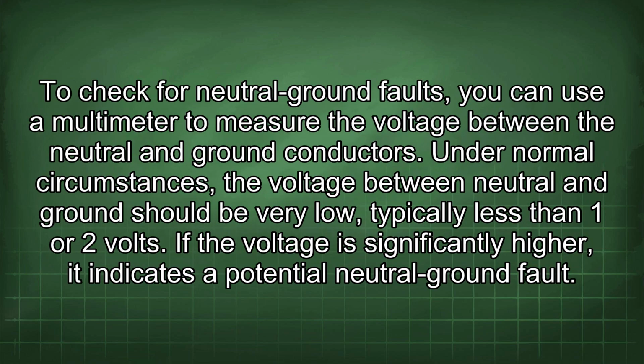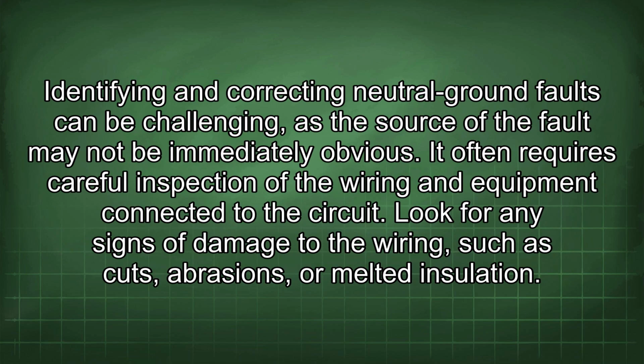To check for neutral ground faults, you can use a multimeter to measure the voltage between the neutral and ground conductors. Under normal circumstances, the voltage between neutral and ground should be very low, typically less than 1 or 2 volts. If the voltage is significantly higher, it indicates a potential neutral ground fault. Identifying and correcting neutral ground faults can be challenging, as the source of the fault may not be immediately obvious. It often requires careful inspection of the wiring and equipment connected to the circuit.